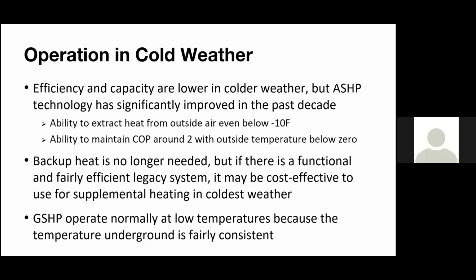So again, if you haven't worked on heat pumps in 10 years, you might think, okay, this can't heat past 20, 30 degrees, which actually was the case a while ago. And then you'd say, okay, well, now we're going to have to bring in backup heat, right? We need some kind of supplemental heat. Let's just bring in a backup boiler. When it drops below 20 or 30, we'll still have our heat pump system. That is really no longer the case. VRF has now been the sole source of heat in hundreds and hundreds of buildings. You do not need backup heat.